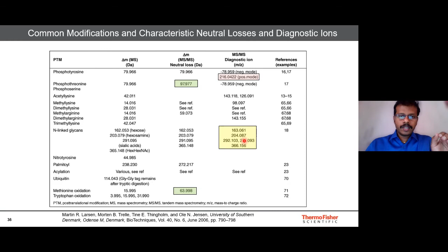Before going to the next one, we have seen dual fragmentation, right? In dual fragmentation, this mass is very, very important, because the mere presence of this mass will trigger the next fragmentation technique on the same precursor. Therefore, we need to be very critical about the mass accuracy at the MS2 level, right? That is where Orbitrap is very important. Here, if you see, this is 84.08 and 84.04. They are near isobaric, right? But 84.04 is the actual oxonium ion, whereas 84.08 is an ammonium ion from an amino acid backbone. Therefore, it's very, very important to have mass accuracy at the MS2 level.